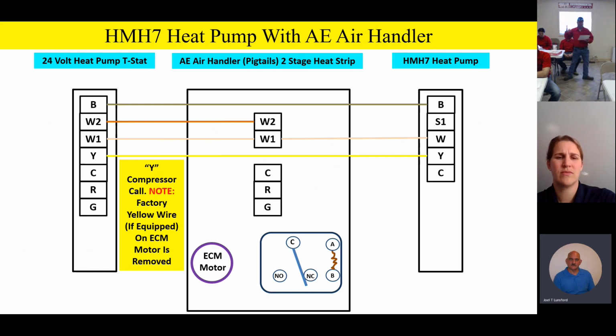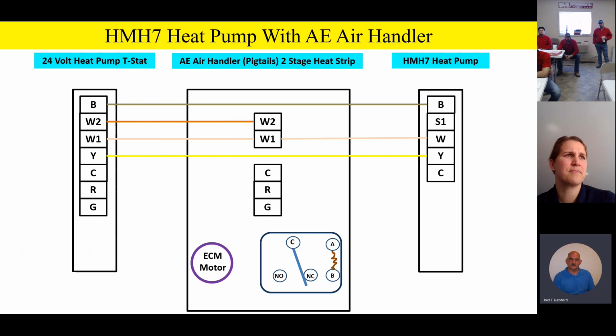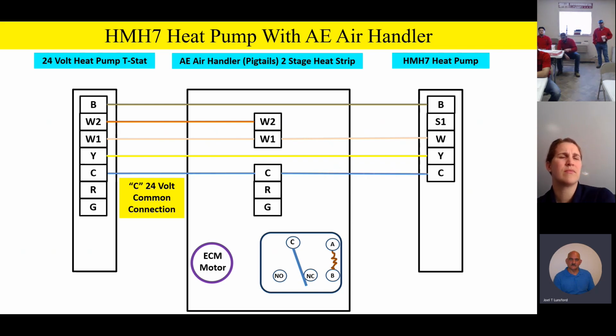You'll also note that on the AE air handler, some models, if equipped, will have a yellow wire on the ECM motor. Go ahead and remove that yellow wire off the ECM motor, because we're going to be utilizing the speed taps on this motor as we need it with the relay and so on. We'll get to that in a little bit. So if it does have a yellow wire, go ahead and remove it. C is 24 volt common. It slides all the way through from the thermostat to the indoor unit to the outdoor unit.